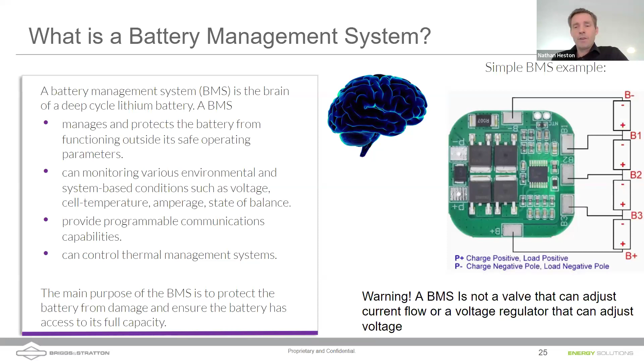Lead acid batteries -- many of us are not familiar with BMS systems because lead acid batteries simply did not incorporate them. These are cheaper batteries that you would essentially get 2 volts per cell on, and they didn't really need battery management systems. The charge versus voltage curve on a lead acid battery is much steeper. You could essentially tell what the state of charge was entirely based on voltage, and you could just trigger your inverter system to react to those voltages.